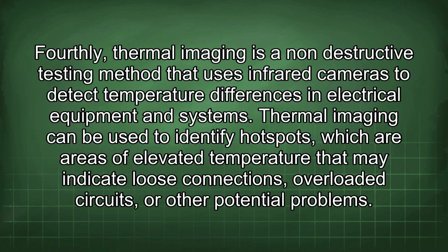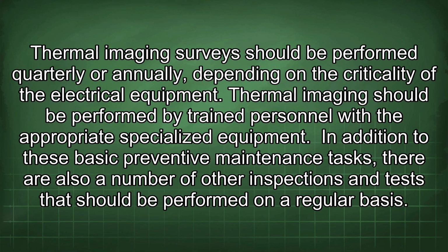Fourthly, thermal imaging is a non-destructive testing method that uses infrared cameras to detect temperature differences in electrical equipment and systems. Thermal imaging can be used to identify hotspots, which are areas of elevated temperature that may indicate loose connections, overloaded circuits, or other potential problems. Thermal imaging surveys should be performed quarterly or annually, depending on the criticality of the electrical equipment.